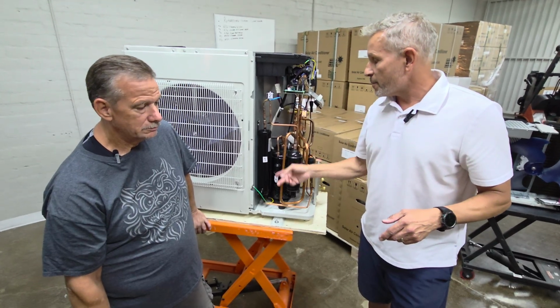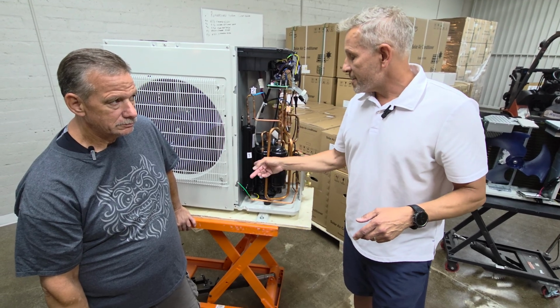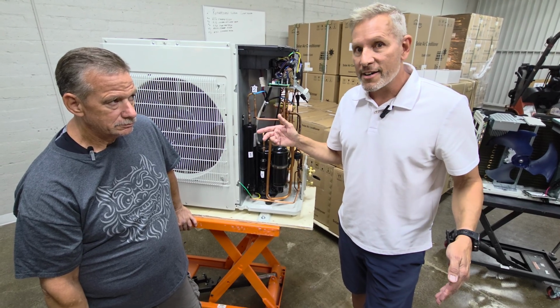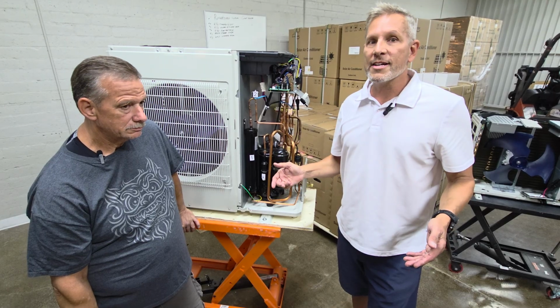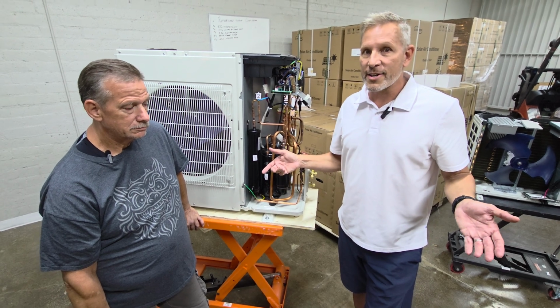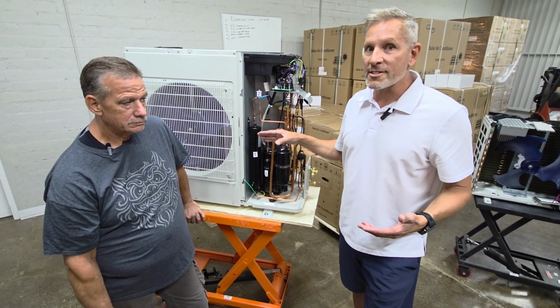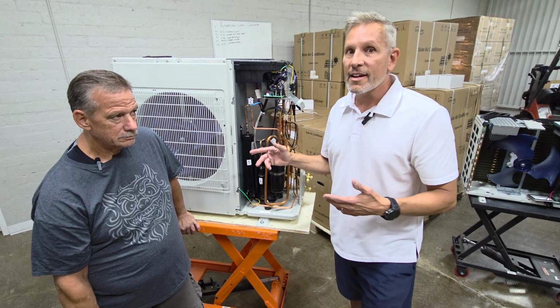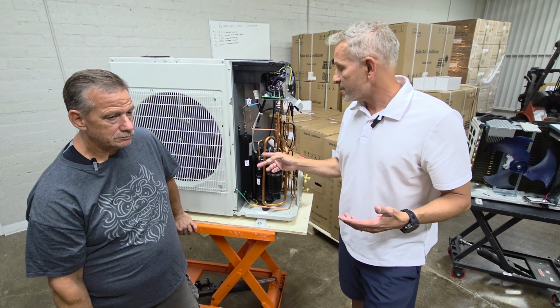All right, and meanwhile, that's the liquid refrigerant before it goes into the outdoor unit here. What about the gas on the other side that's going back to the compressor? Well, that's getting warmed up by making the refrigerant on the other side of the barrier colder, and that's good news because the compressor is becoming warmer. You can imagine a machine trying to do compression when it's getting refrigerant back at about minus 20 degrees Fahrenheit. Not going to happen very easily. So this pre-warms the compressor such that when the main refrigerant loop comes back to the compressor, it mixes, and so now you're running at a little bit higher temperature and a little bit higher pressure, both of which are good to allow the compressor to run.